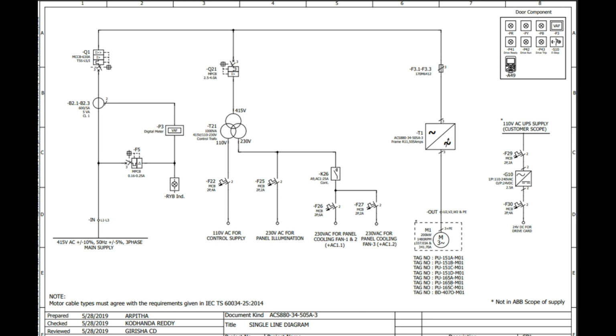So this notation is very important. This notation will be used further in the drawing. Q1 is for MCCB, that is the main molded case circuit breaker, and the rating here you can see is 630 amps. It will vary based on the rating of the drive.